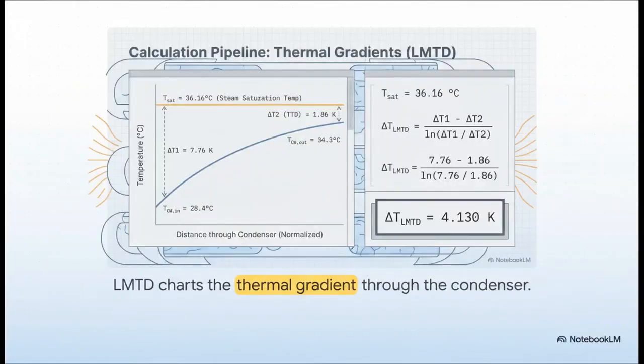First up, the log mean temperature difference, or LMTD. This basically charts the thermal gradient right through the condenser. That orange line at the top, that's our steady steam saturation temperature sitting at 36.16 degrees Celsius. The blue curve traces our cooling water. It enters at 28.4 degrees, absorbs the heat from the steam, and rises to 34.3 degrees by the time it exits. By plugging these temperature deltas into the LMTD formula on the right, we get a normalized thermal gradient of 4.130 Kelvin. And let me tell you, this is the absolute driving temperature force of our entire condenser.